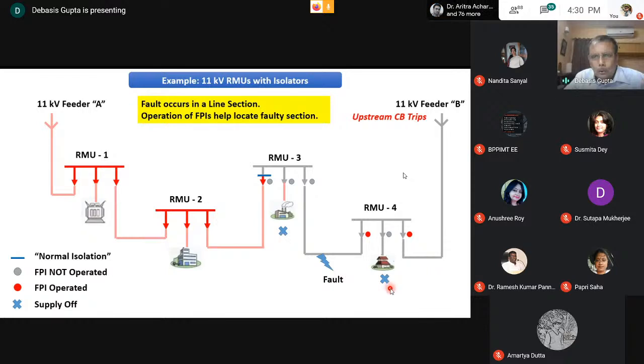Now, how does an engineer know from remote if it is automated, or when they physically go, where is the fault? All they do is go and look at the FPI. You can see, because the fault current is being fed from here, the path is like this. So this FPI will operate, this will operate, this won't operate. Similarly these won't operate because the fault is on this side. So normally we look at a section where on one side the FPI has operated and the other side it has not operated - it means this is the unhealthy or faulty section.